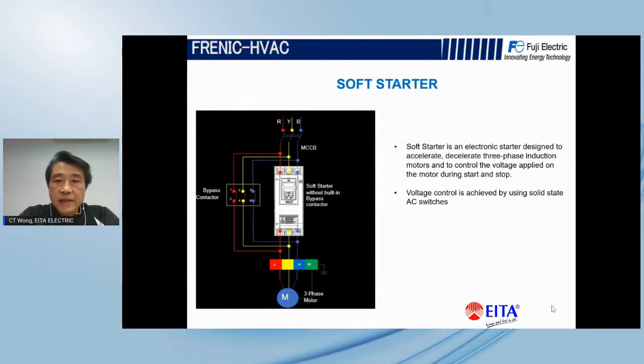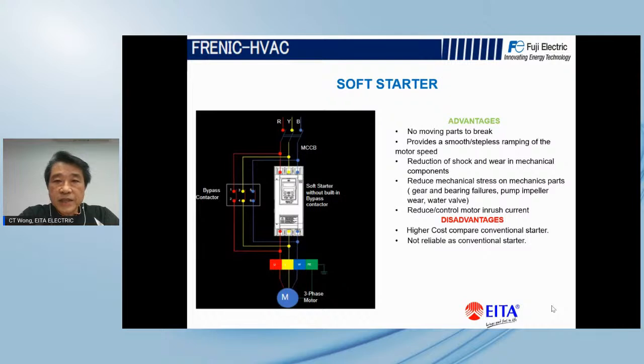Soft starters, I can see that this is the latest technology. It's an electronic starter combined with thyristor technologies. The advantage of soft starters is basically that there is no moving part, compared with conventional star delta, where you need a contactor, which is a moving part. It's also much smoother, because the acceleration varies according to the voltage and time. It's not like the others, which basically cut in at 50% or 75%. Of course, when it is smooth, there is a reduction of shock on the mechanical side.